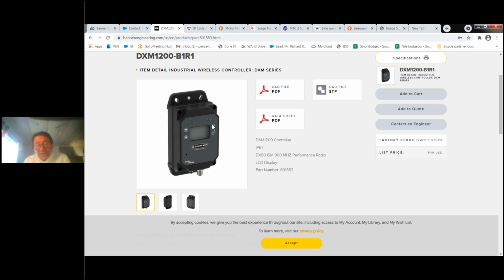We have the ability on the IQ product for up to 8 digital inputs and 3 analog inputs. We also have a pulse train input for pulse flow meters. So you don't even need to go to the unit from the radio manufacturer that has I/O. You just use the drive as an I/O port. That's a really nice thing about the Yaskawa product. We've had this extra I/O that you can use. And you have the ability on the drive to add an additional 16 digital inputs or another pulse input for 2 flow meters or some more analog inputs. So the drive can be your data collection center, and you can stay with the simple robust radio.